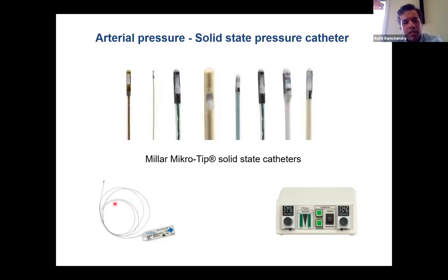Usually the scenario is that you have this solid-state wire where the tip, as showcased here, is what measures the arterial pressure. That goes inside the animal, and the other end gets attached to a pressure box, which then gets converted. There is a lead that goes out to your A/D conversion that you can look at on your screen using either LabChart or Spike or whatever program you might use.